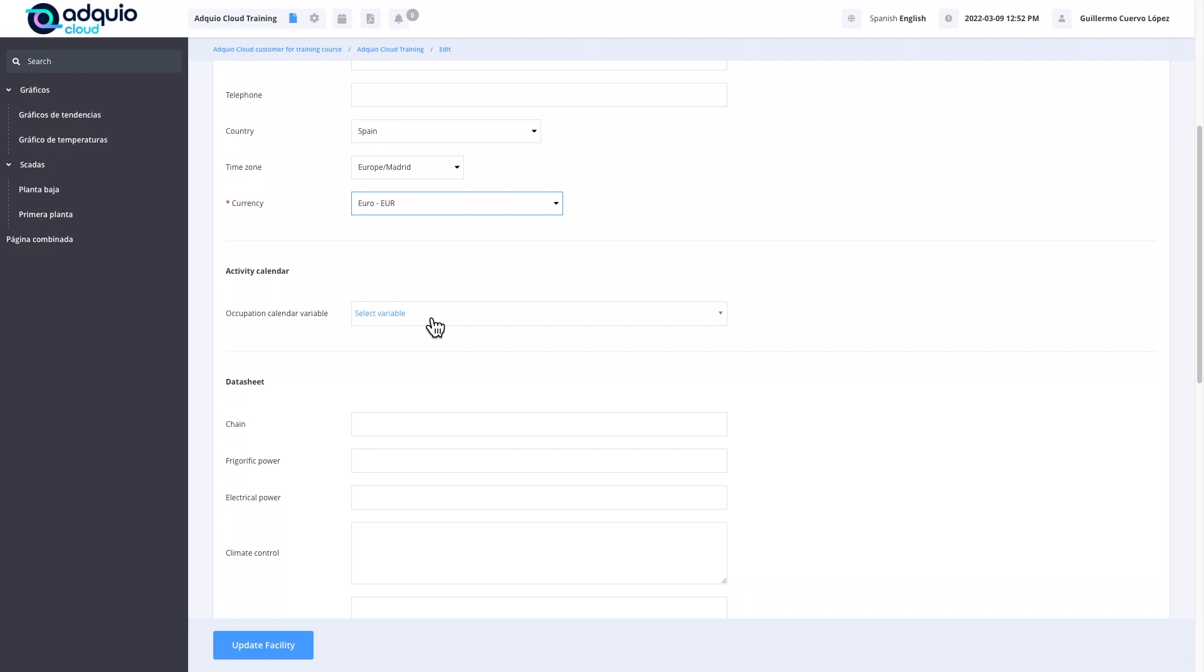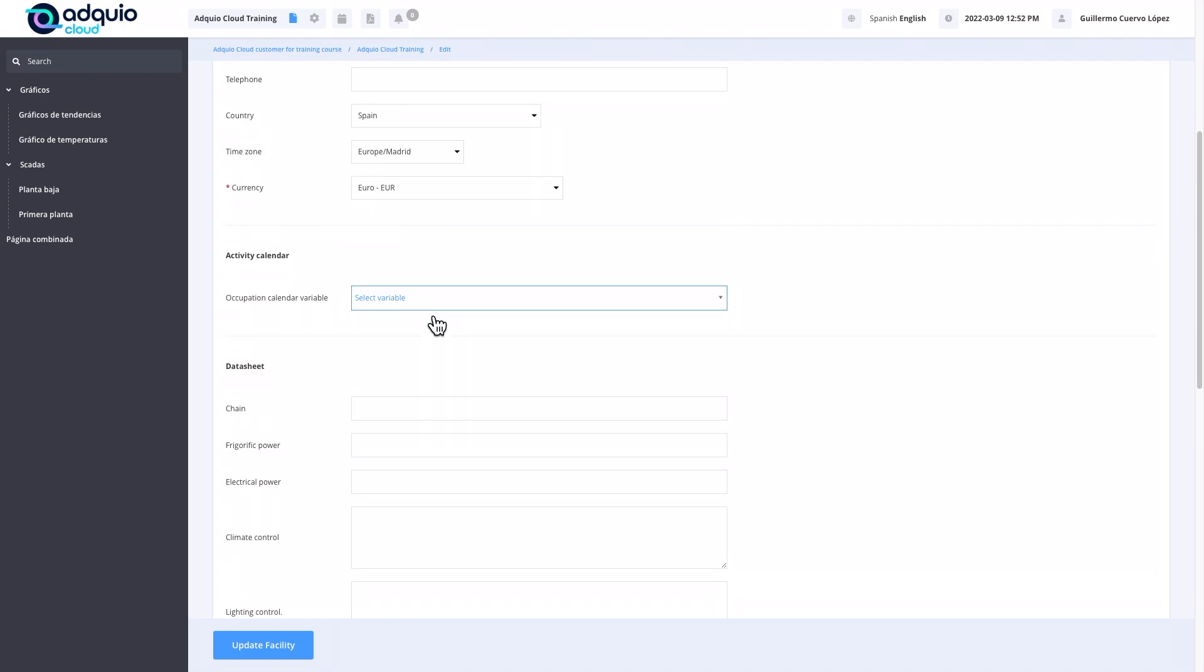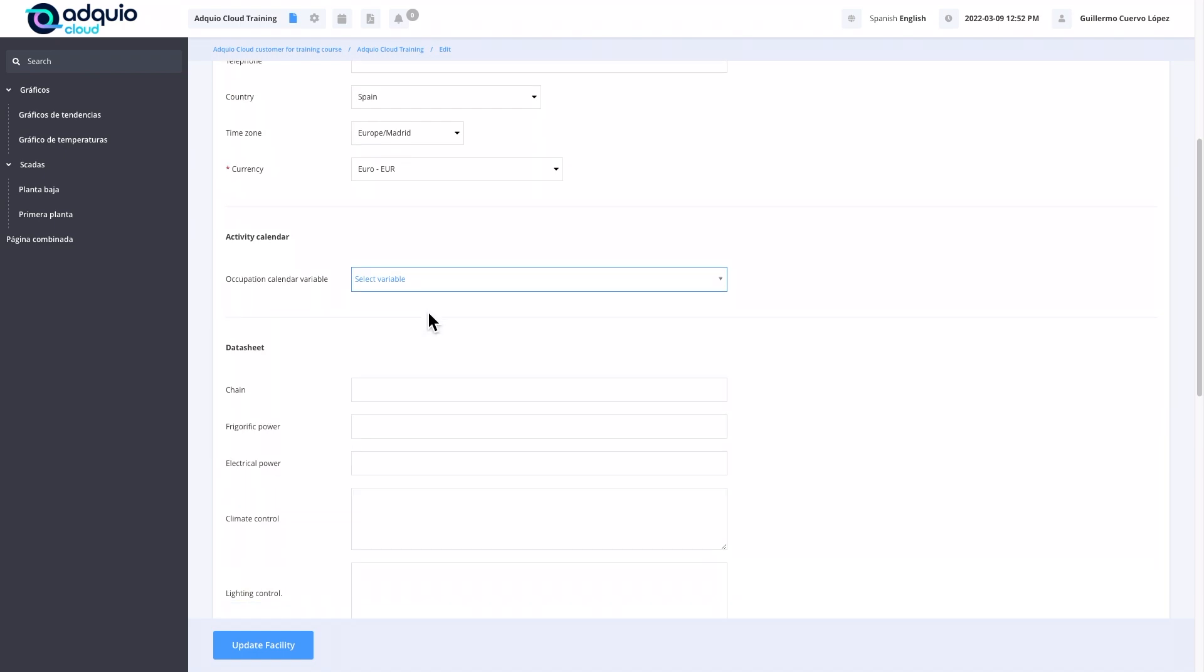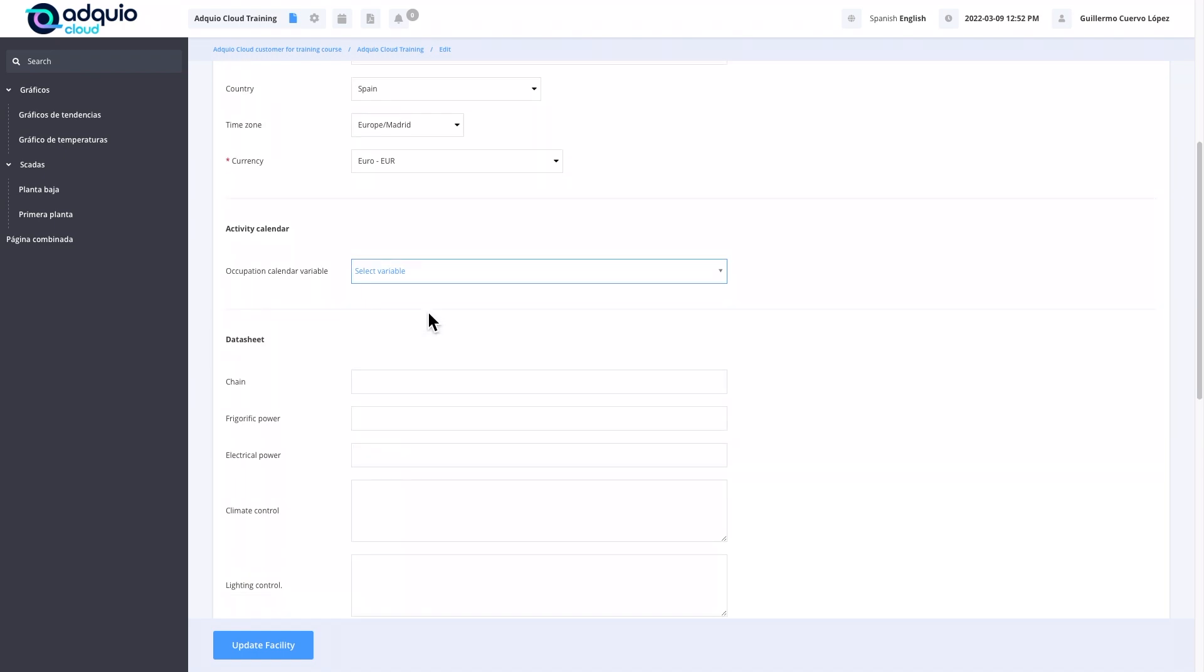The occupancy calendars: Adquio Cloud allows us to define based on a variable if our facility is occupied or not. This allows us to draw graphs according to occupancy, for example, take graphics when the room is busy and when the room is empty. This is important because if we want to obtain data on climate or climate consumption, it does not make any sense to mix occupancy with when the place is not occupied. The average of those values would not make any sense if the machines are turned off, so we can differentiate and graph separately the data when the premises are busy and when they are unoccupied.